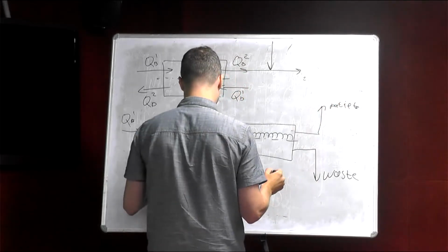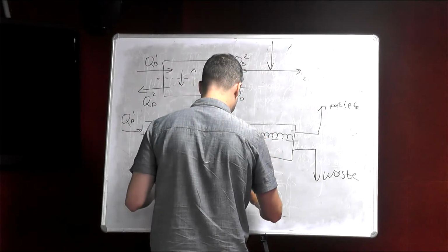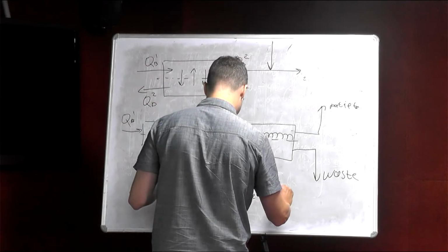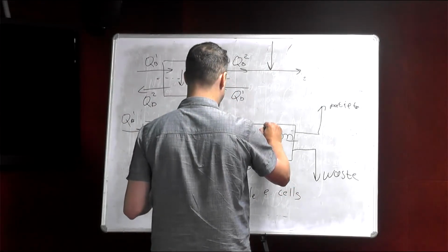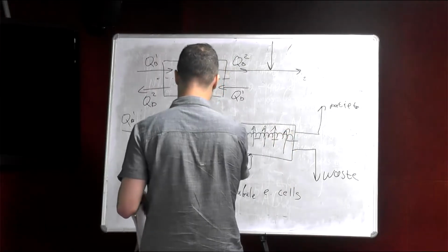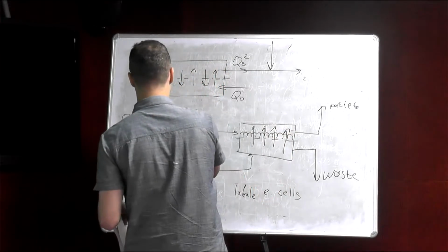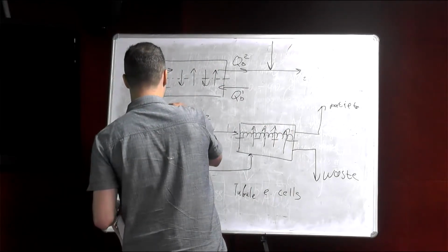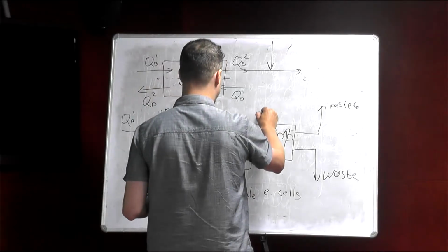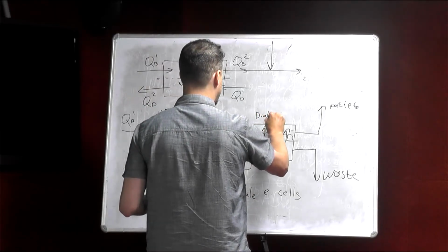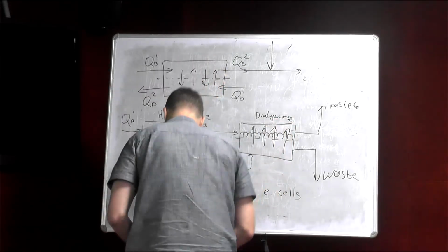Those are usually tubular epithelial cells that provide the reabsorption of nutrients back to the blood from the initial ultrafiltrate that we removed from the patient. And this hemofilter works as the glomerular capsule, while this modified dialyzer works as the improvised proximal convoluted tubule.